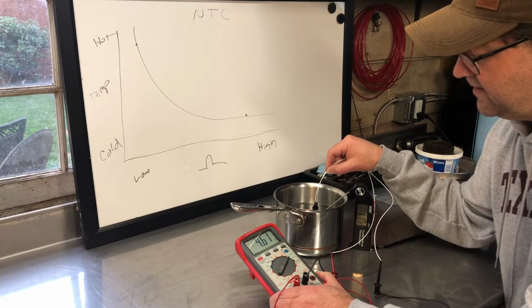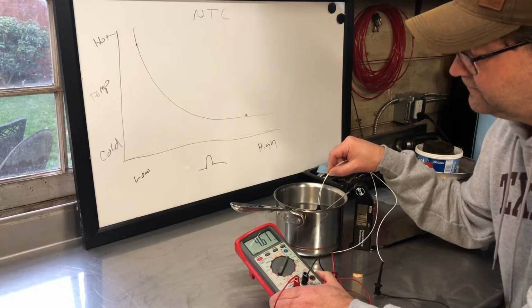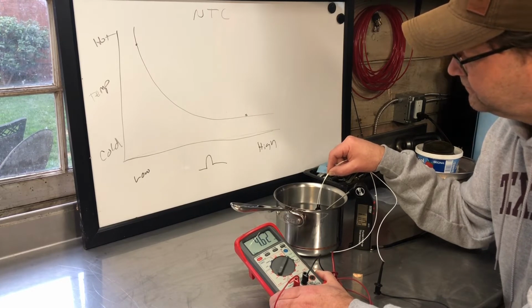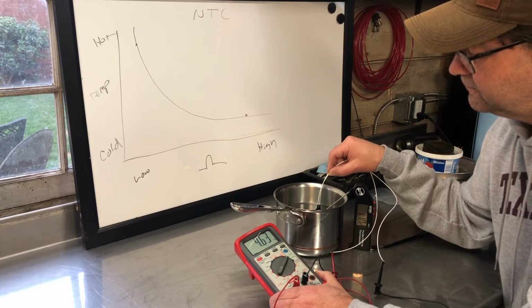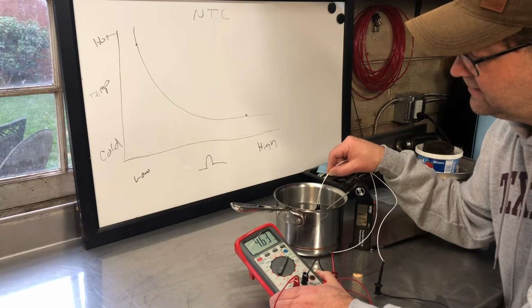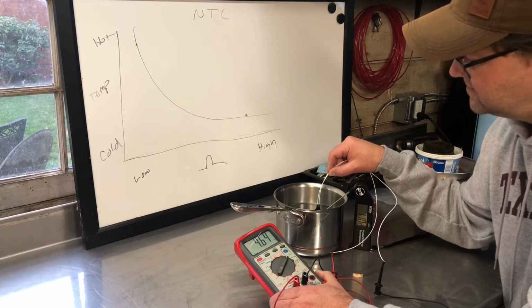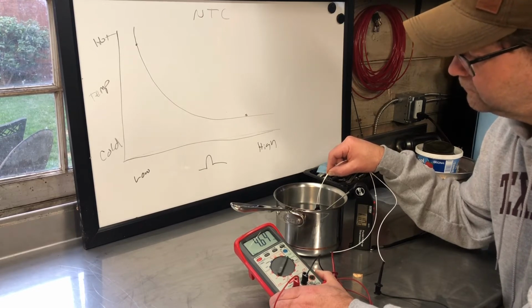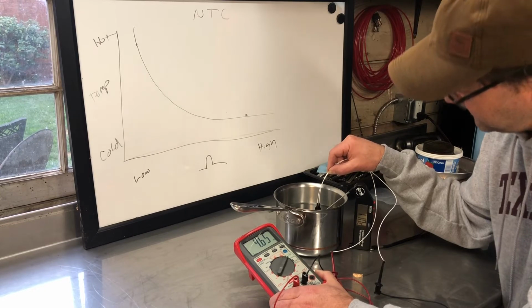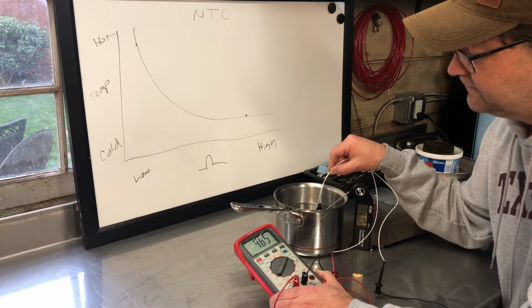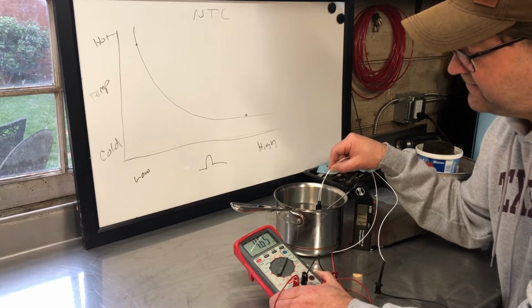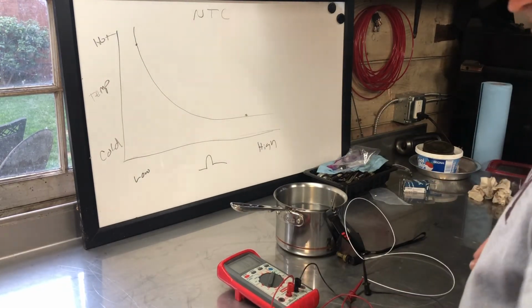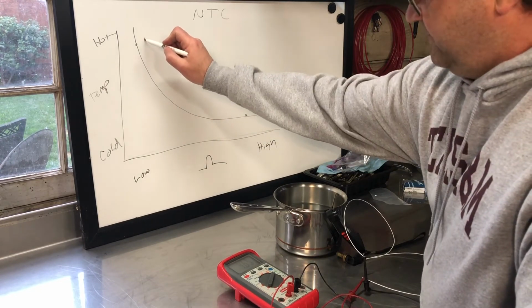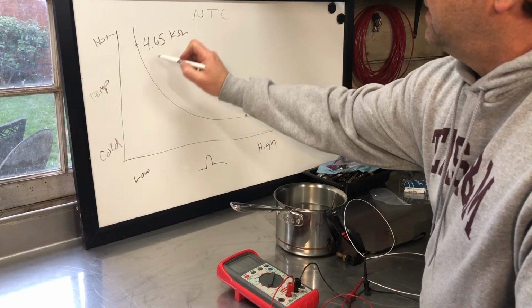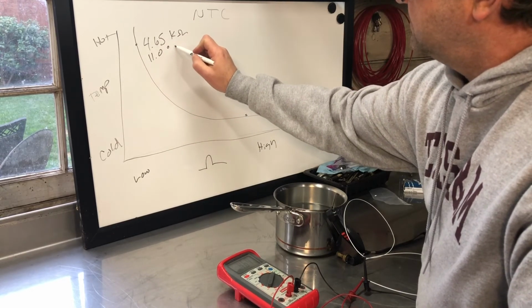So I'm going to wait for it to slow down and maybe even turn around before I take a reading. .63 kiloohms, slowing down. 4.64. 4.65. 4.65. We're still at 11.0 degrees. I think we're going to call it good right there: 4.65 kiloohms at 11 degrees Celsius. So I'm going to write that on my low temperature: 4.65 kiloohms at 11.0 degrees Celsius.